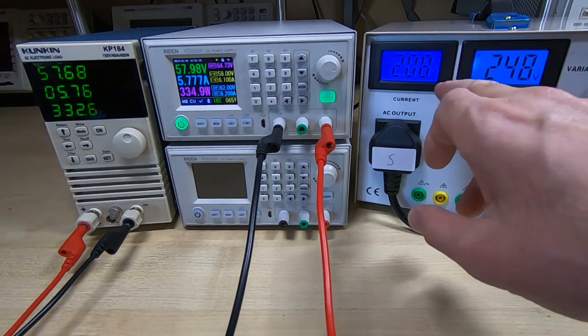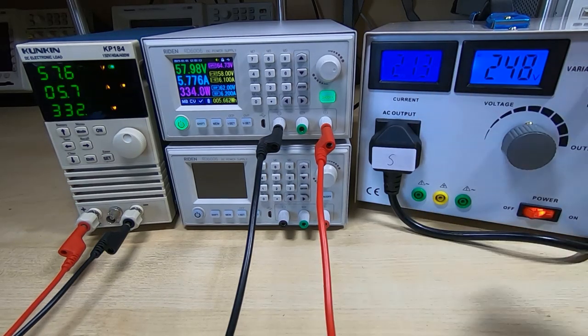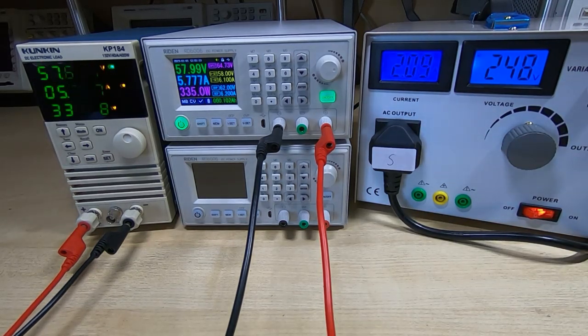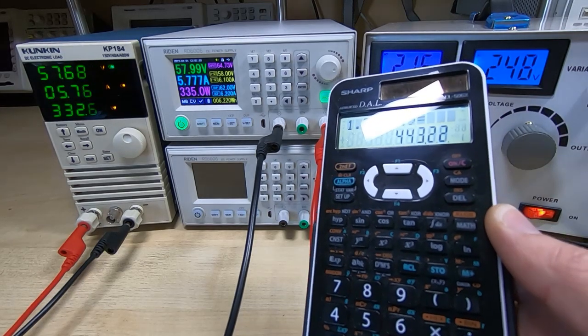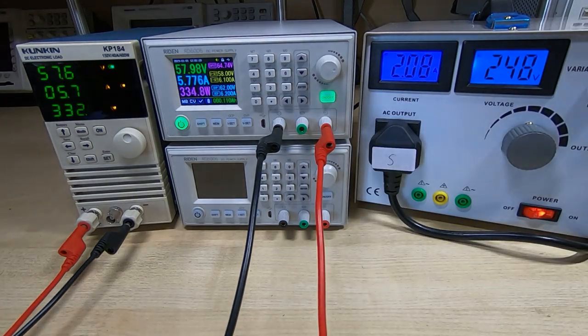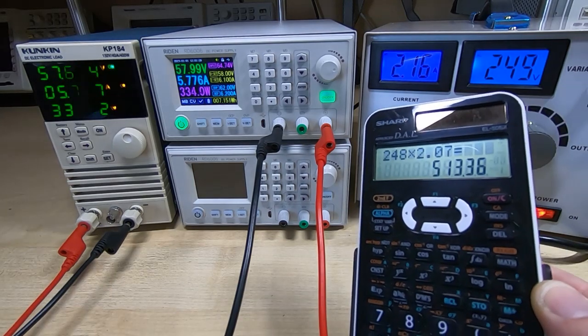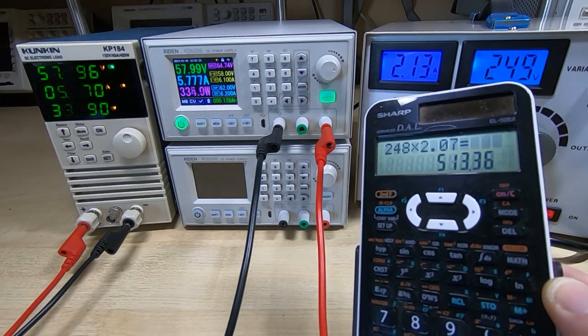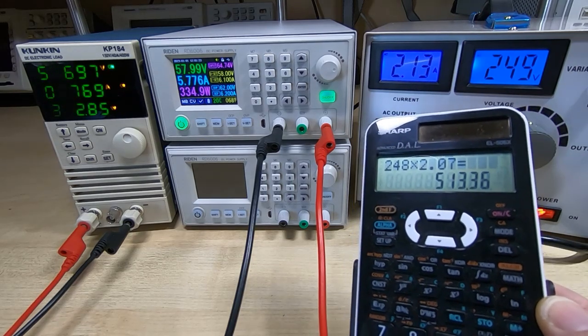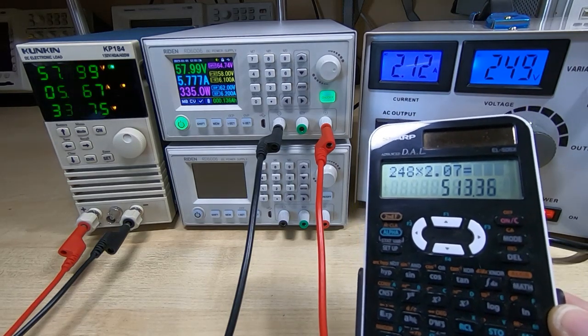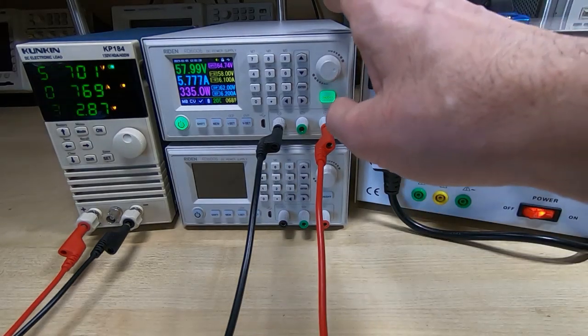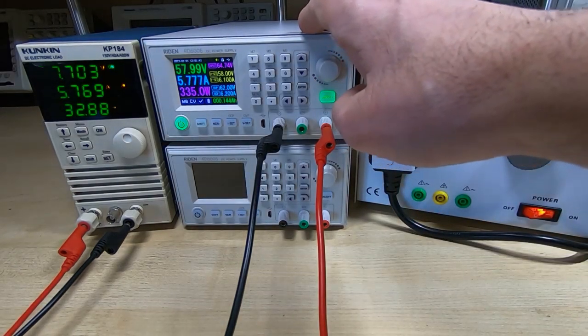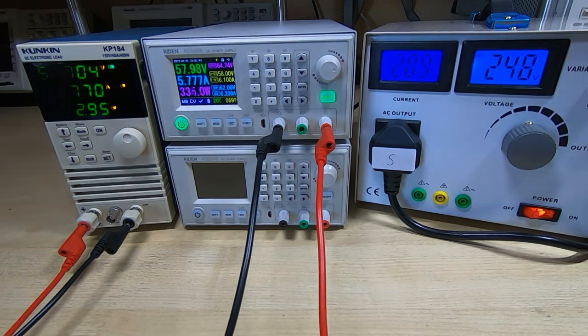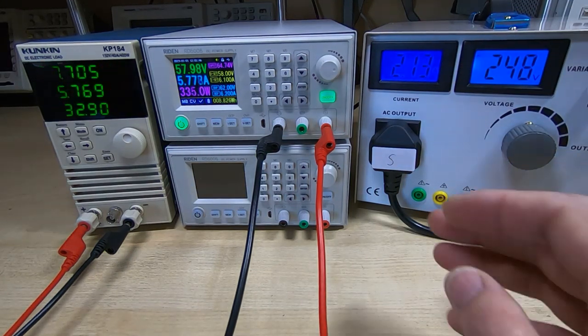This will continue to rise to quite a high level. Remember, before we were getting an apparent power of 443 watts. If I work this out now, 248 times 2.07 gives us 513 watts. That's a huge difference — getting on for 100 watts more apparent power — and that's because the power factor this switching supply creates is far worse than the linear version.